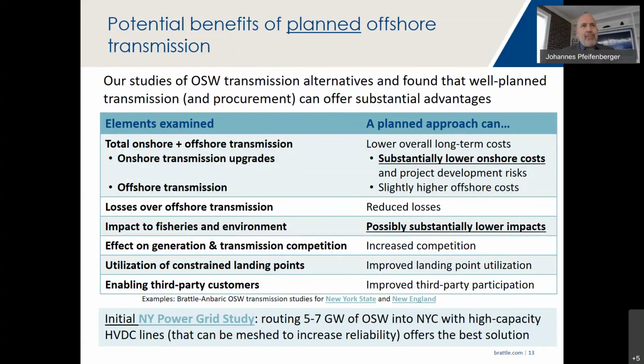By having a plan to switch to larger procurements that can use HVDC lines, you reduce the transmission losses of moving power from the wind farm, which might be 60 miles away, to the shore. And by planning to use larger transmission lines, you also have less impact on fisheries and the environment, and fewer shore crossings. If you bid it out separately, you might increase competition for the transmission build. And what folks have found in Europe is that if you pre-build transmission, you actually get a more competitive solicitation for wind generation, because not every wind generator has to worry about permitting the transmission line all the way to shore.